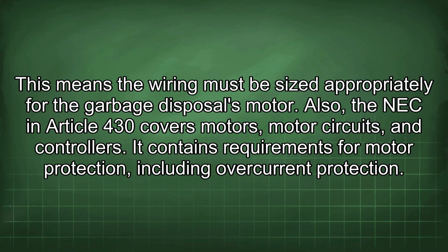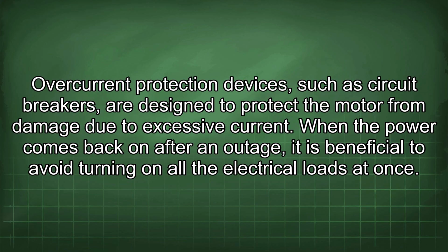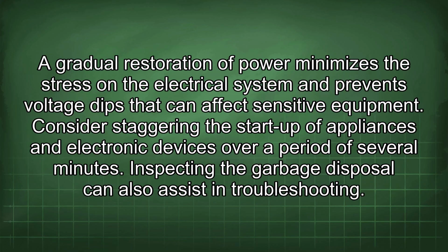Also, the NEC in Article 430 covers motors, motor circuits, and controllers. It contains requirements for motor protection, including overcurrent protection. Overcurrent protection devices, such as circuit breakers, are designed to protect the motor from damage due to excessive current. When the power comes back on after an outage, it is beneficial to avoid turning on all the electrical loads at once. A gradual restoration of power minimizes the stress in the electrical system and prevents voltage dips that can affect sensitive equipment. Consider staggering the startup of appliances and electronic devices over a period of several minutes.